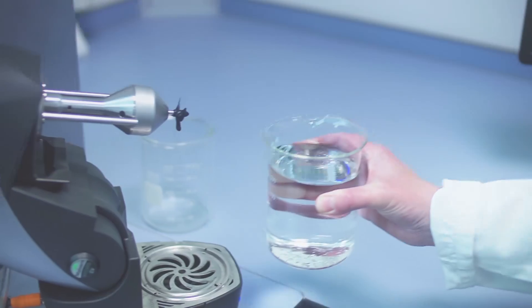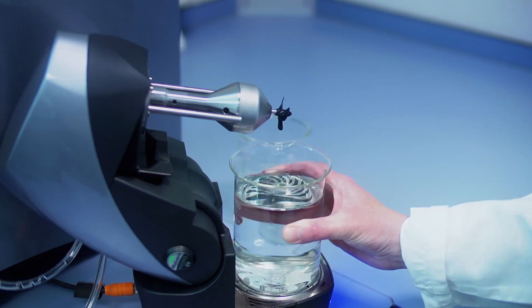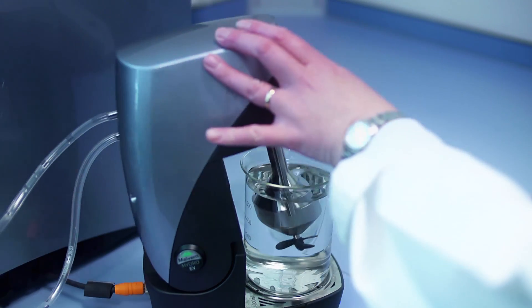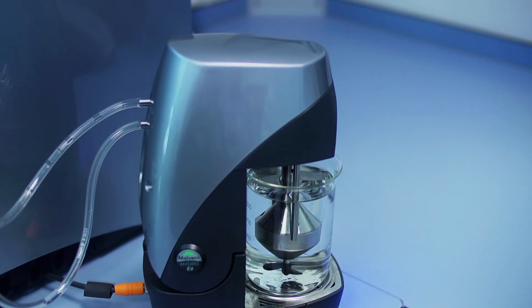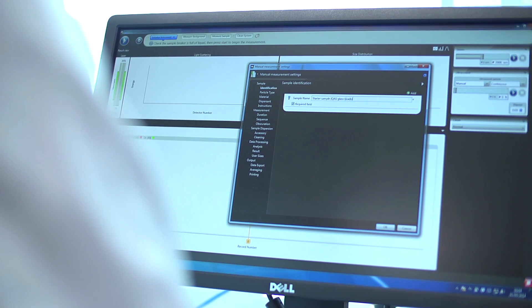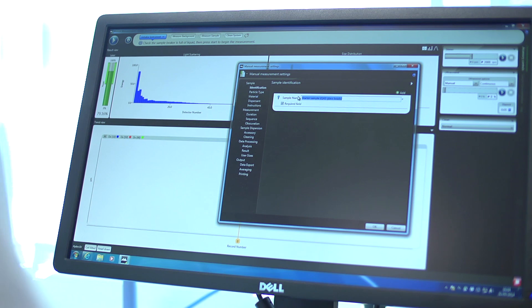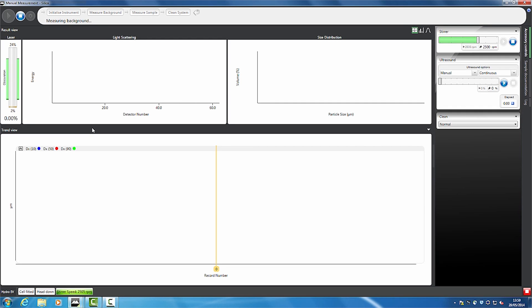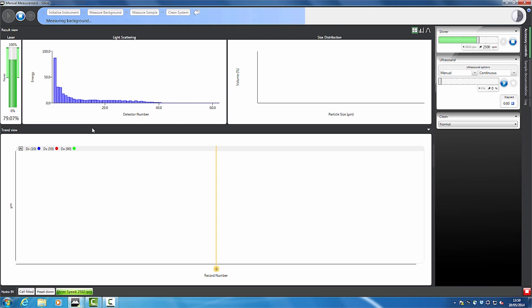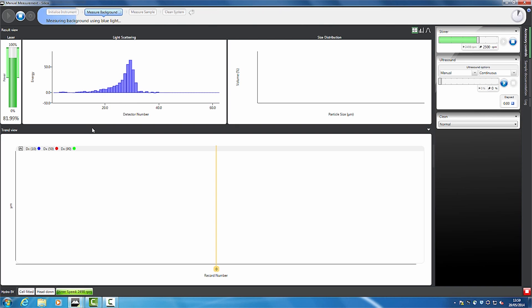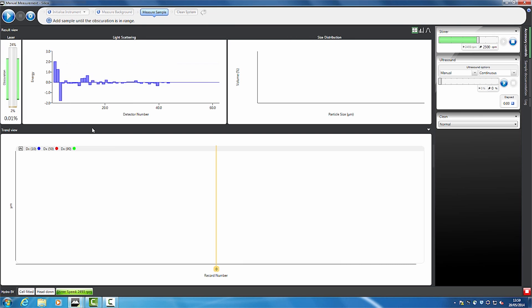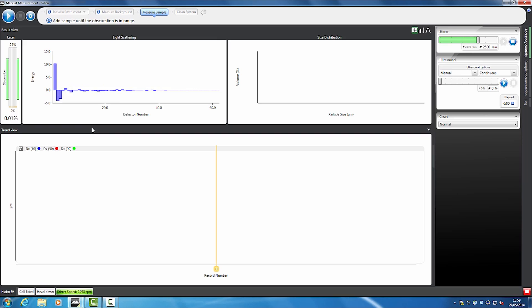The Mastersizer 3000 system and its software has been designed to make method development easier. The Mastersizer 3000 measurement manager provides a view of everything you need to understand and optimize the measurement process. This includes controls for the dispersion unit, live reporting of the data being collected by the system, trending of the results, and a simple view of where you are in the measurement process.